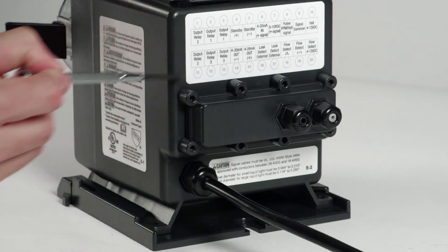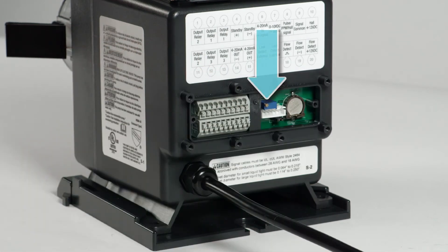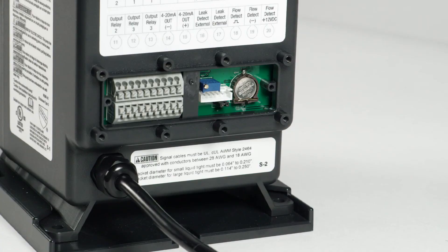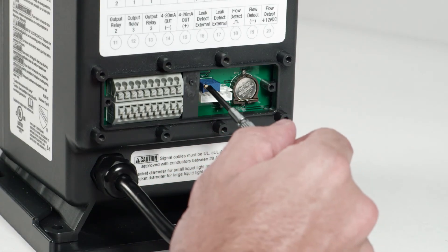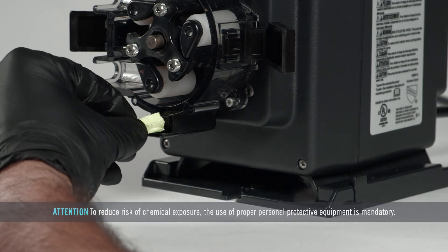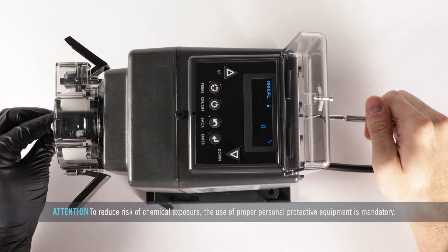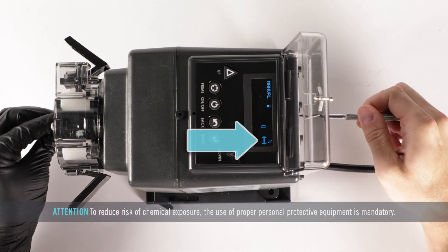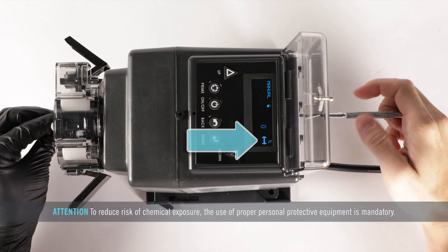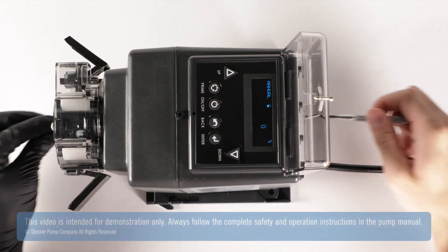Remove the eight screws and the signal cover from the back of the pump. The brass screw is the potentiometer. Place a flat blade screwdriver in the potentiometer slot and at the same time place a sponge with chemical on the pins. Slowly turn the potentiometer counterclockwise until the tube icon appears on the display and is not flickering. Then turn the potentiometer slightly past this point and calibration is completed.